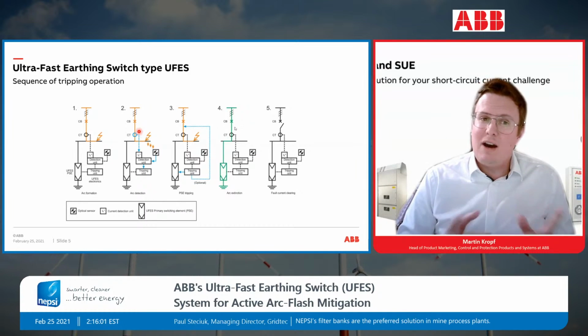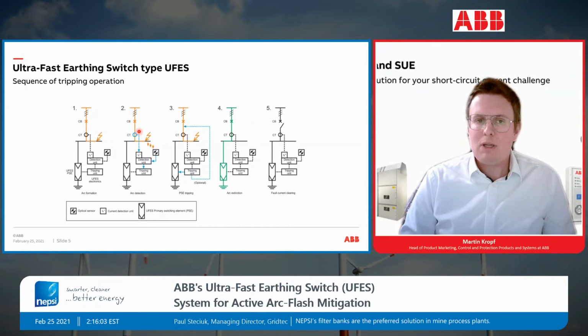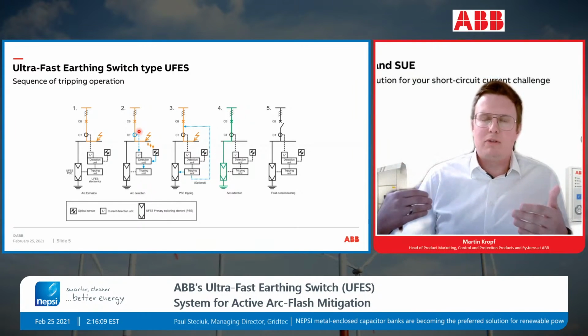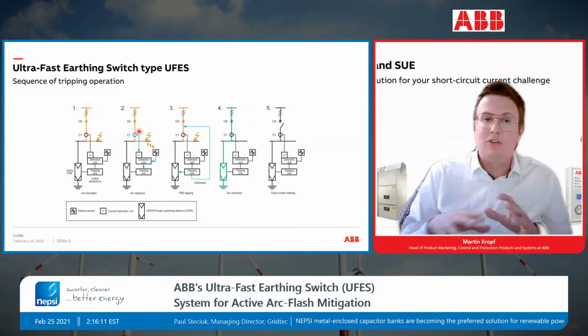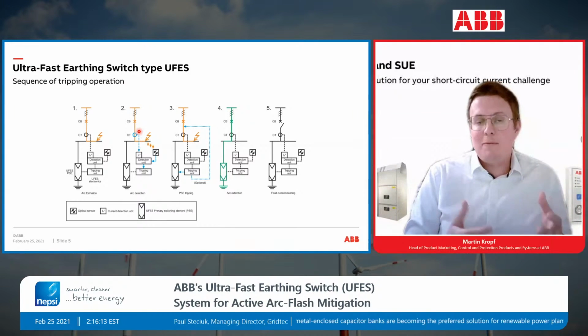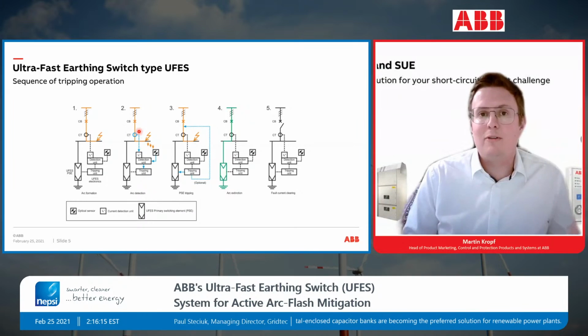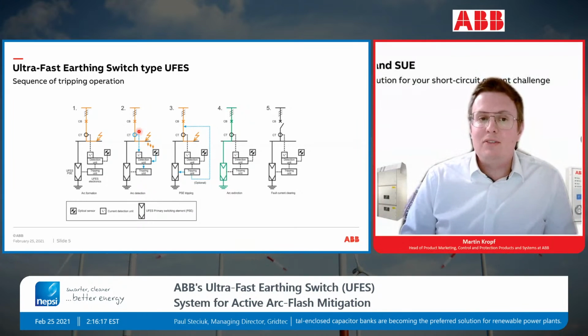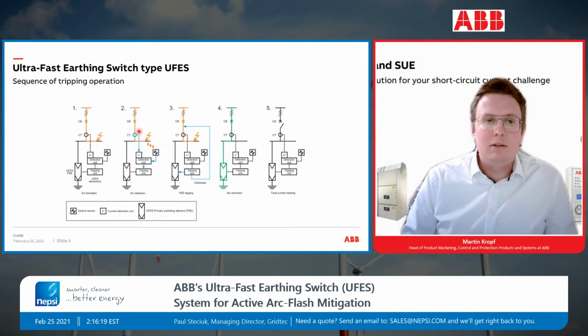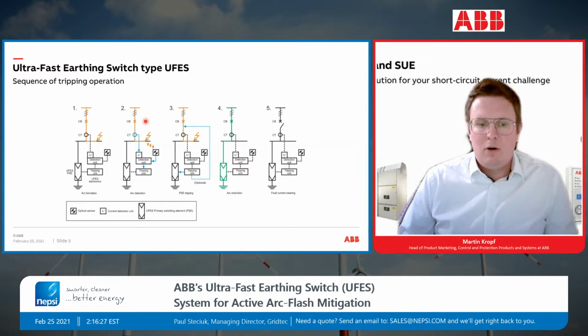If we go only current, it's possible, but then it's just clear that we are also tripping if there is an external fault. If there is an external fault somewhere, not an internal arc, we are also tripping, since the tripping criteria of current might be fulfilled. And this could be done if we want to do this, or if we just want to focus on the internal arc. As I said, it would make sense to have the logical AND. So in step number 2, we have understood it's an internal arc.